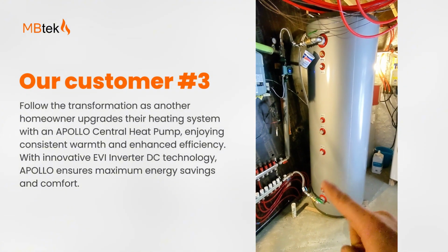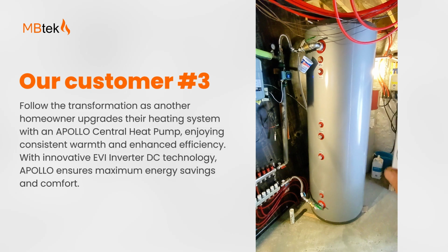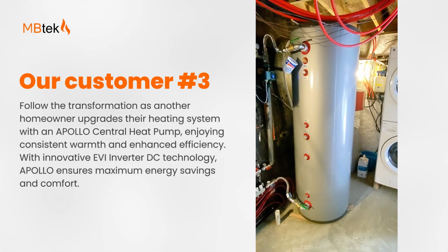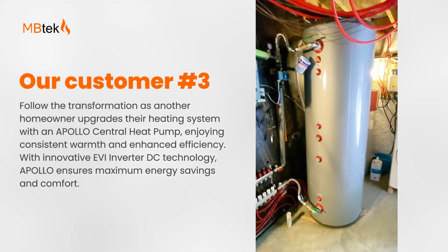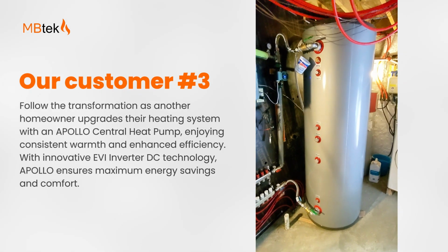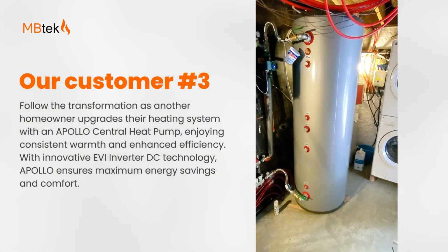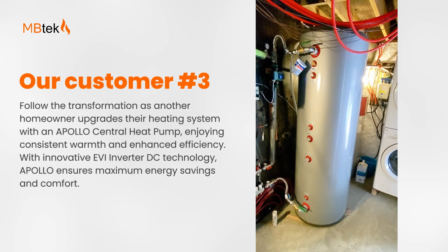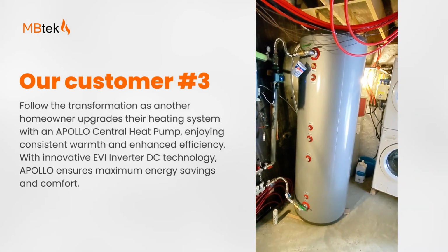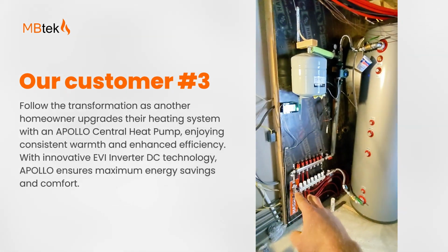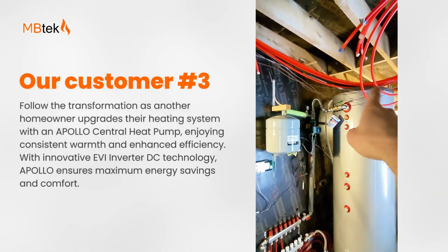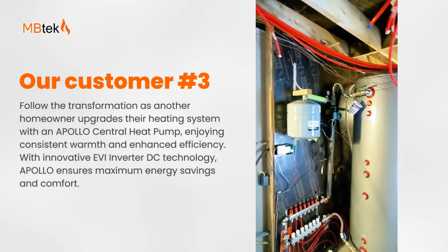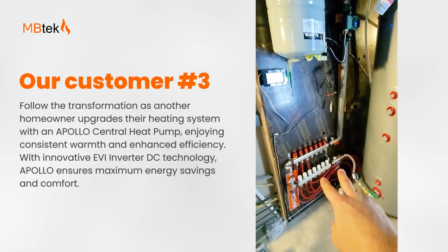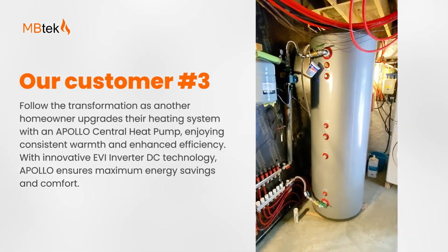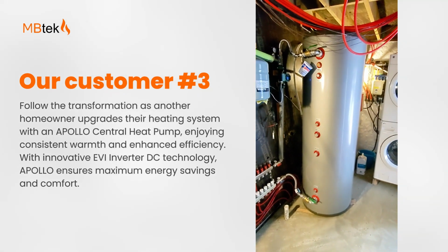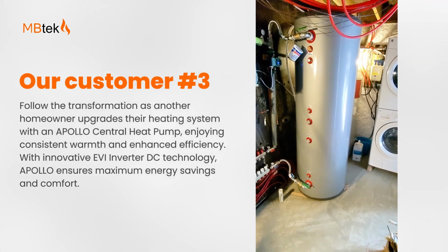So again, the bottom heat exchanger coil is the dedicated heat pump loop, part of the heat pump loop. That whole loop holds about 8 gallons of fluid, out of which 4 gallons is propylene glycol. So I bought for $120 a 5-gallon bucket of propylene glycol. Now, if my entire system, everything in the buffer tank and everything going into my radiant floor, and then later on to my hydronic radiator panels in each bedroom, which these lines are for that are not hooked up yet in my manifold, if everything was running on glycol, I'd be spending a fortune on glycol every 5 years, because about every 5 years you're supposed to replace the glycol because it breaks down.